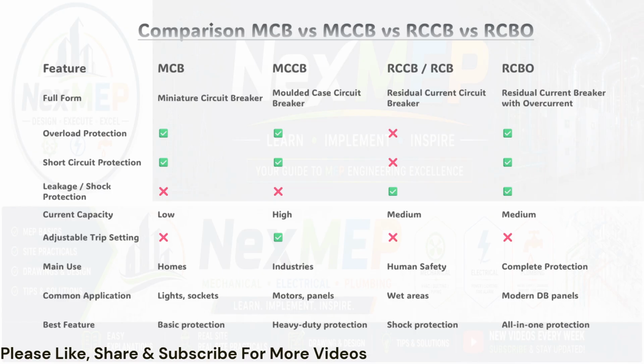And the RCBO ticks every box: overload, short circuit, and leakage. No adjustable trip setting, but it gives you all-in-one protection in a single device, ideal for modern DB panels. So when you're selecting a breaker on site or during design, always ask, what am I protecting: equipment, cables, or people? That answer will tell you which device to use.